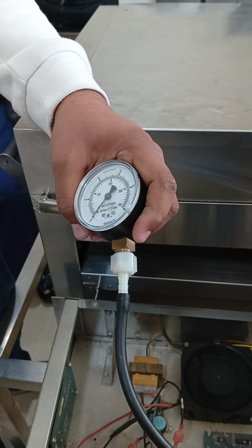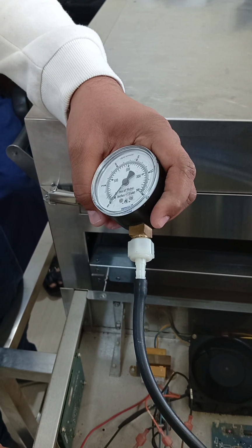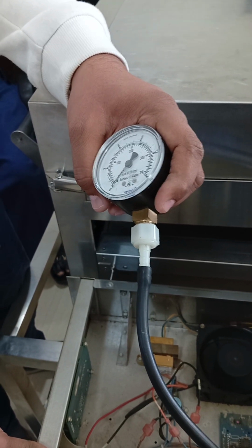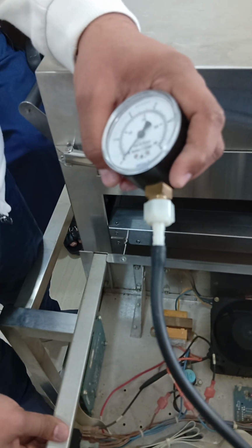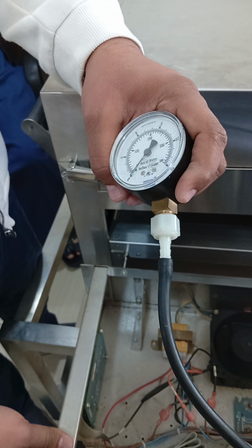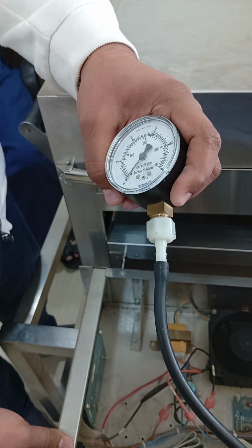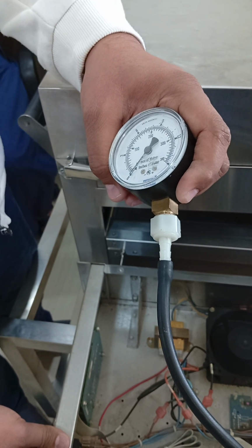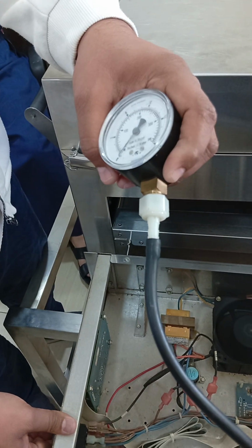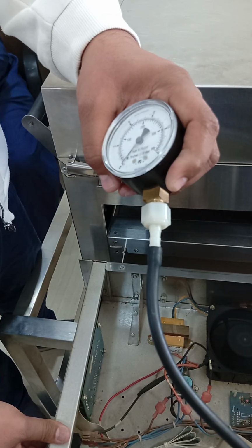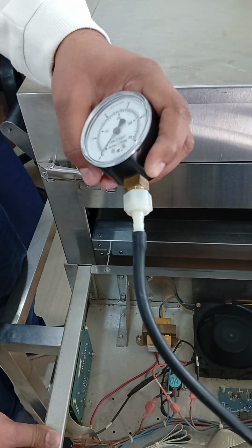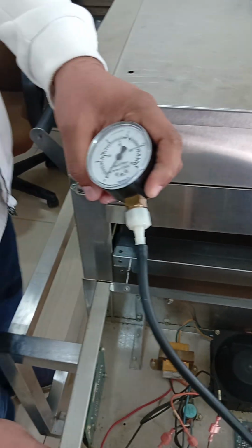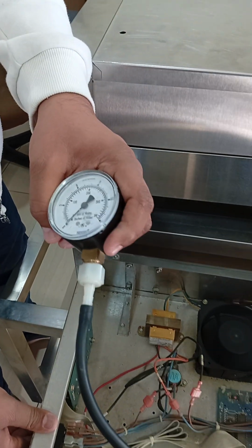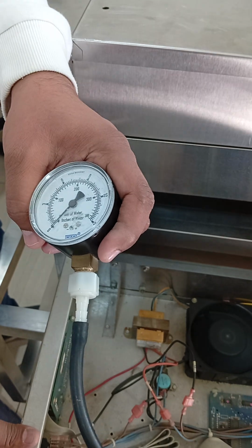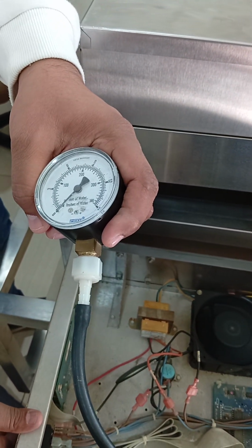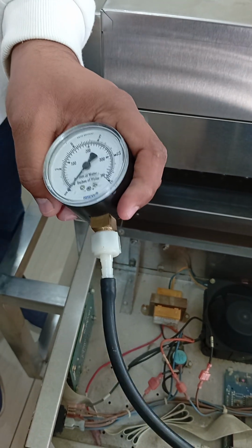So just wait for ignite. Sometimes purge. Oh, no. Now no. Ignite. That's the purging for 30 seconds, and then now ignite. Yeah. Wait, stay. Yes, perfect. First time it used to fail. Now it worked. Okay. Increase the pressure. Increase. Now increase three times, then the gas will come up. Maybe it fails two times.